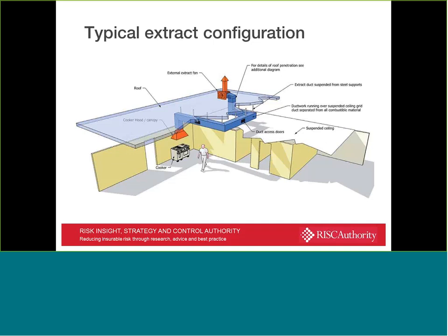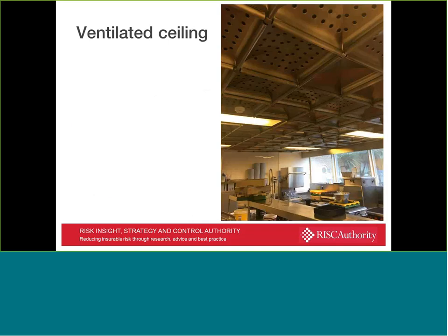and it could be argued certainly in terms of this diagram that the ductwork doesn't necessarily take the shortest and most direct route to the outlet, so there may be opportunities for improvement there, because the fewer turns you have in the ductwork, the less likely it is to catch grease. And similarly, we're showing a system here with squared corners, whereas you're going to get a far better flow of air and movement of grease out of the system if you don't have corners such as that in itself.